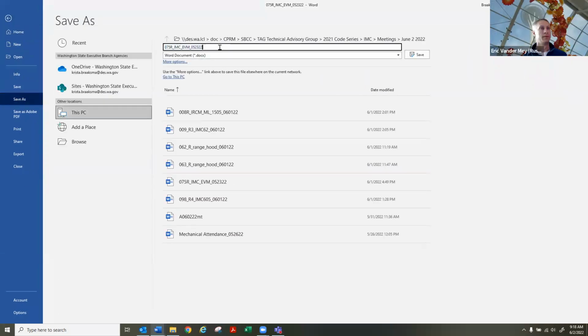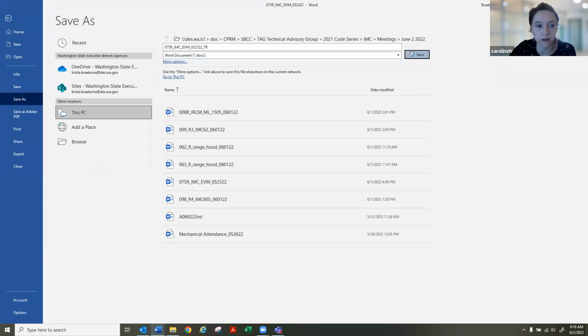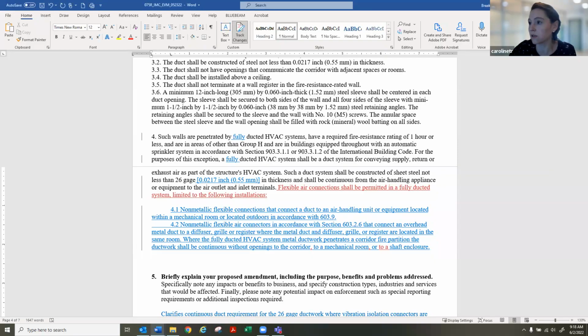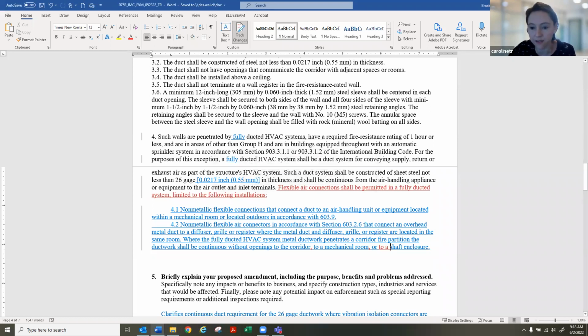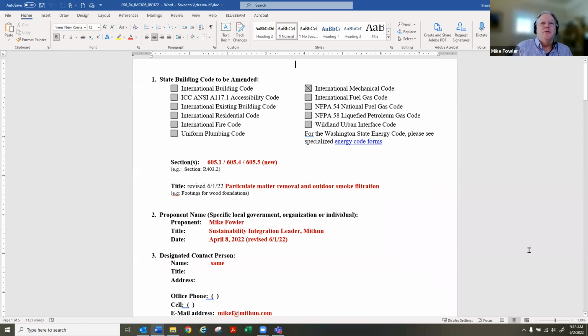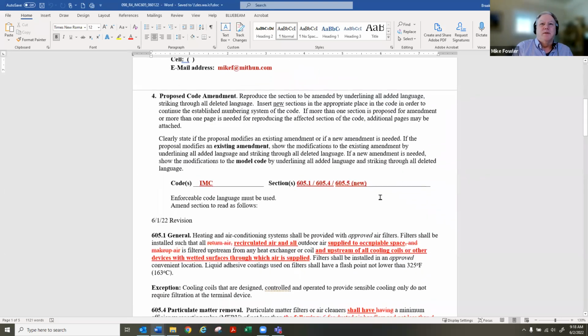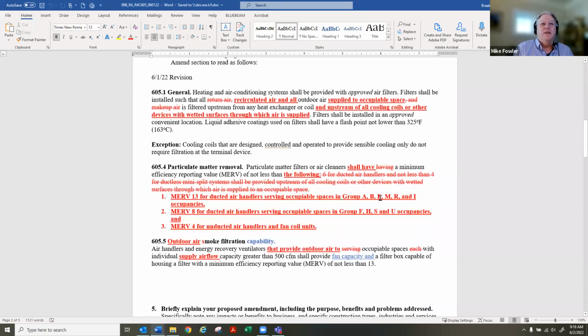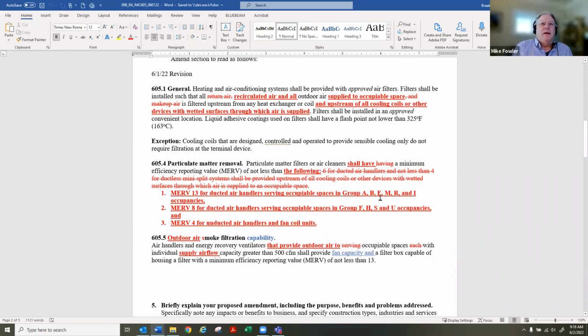Great. So I think next up is the proposal about filtration. And so, Mike, I think you're in the hot seat to catch us up on what changes you made and why. Yep, thank you. Good morning. All right, so our travels have been, when this was first presented, this proposal was looking to delete the recirculation exception in 605.5. Input from the TAG suggested that there should be a specific list of equipment that should have an exception. And this proved out to be quite difficult to do in clear and effective code language. There was some additional input from the TAG members. There's some interest in how California has incorporated MERV 13 filtration into their code.